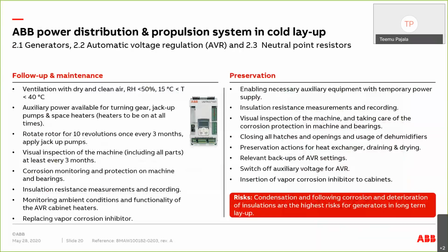and also to have the space heaters. Otherwise, there is no need to have any power on the generator, but the auxiliary power is needed for space heaters continuously and for other equipment when they are used. And then corrosion monitoring and protection on machine and bearings. That's important. And especially for generators and the shafts, some mechanical components, chemical inhibitors should be used on the shaft to treat the surfaces to avoid any corrosion there.